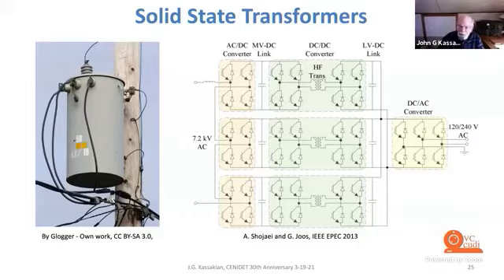The differential in cost is overcome to some extent by the fact that a solid state transformer also provides control capability, which you don't have with the conventional transformer. Some conventional transformers have tap changers, which allow a very limited degree of control. But with a solid state transformer, you've got almost unlimited control to exercise things like voltage lift, load shedding, or browning out parts of the grid if it's overloaded. So there are benefits that compensate to some extent for the increased cost.